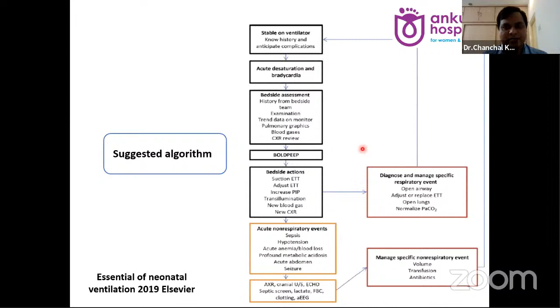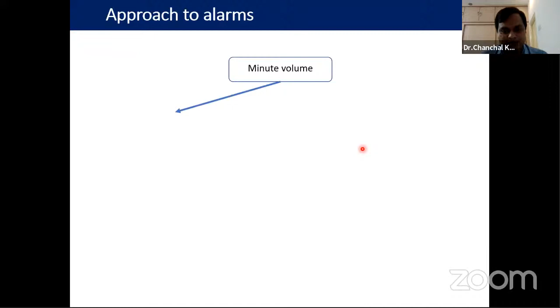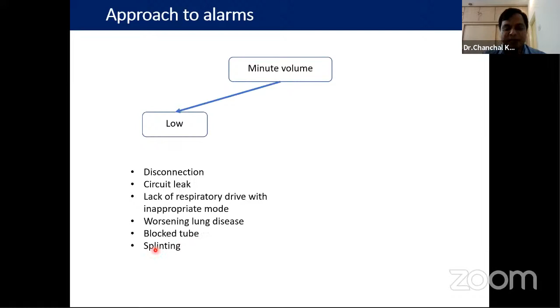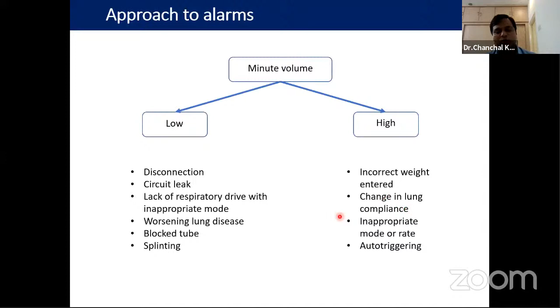The last thing is the alarm, which is part and parcel of the systematic approach. We should always set our alarm appropriately, and we should always respect the alarm. It should never be ignored. There are a few examples of alarms. If the minute volume is low, then this could be because of disconnection or a large leak in the circuit, or because of lack of respiratory drive, worsening lung disease, complete endotracheal tube block, or splinting also. If the minute volume is high, then this could be because of incorrect weight entered, a change in lung compliance, an inappropriate mode, or auto triggering.